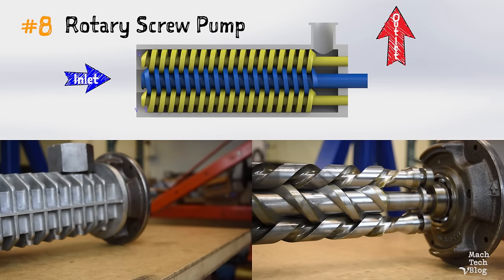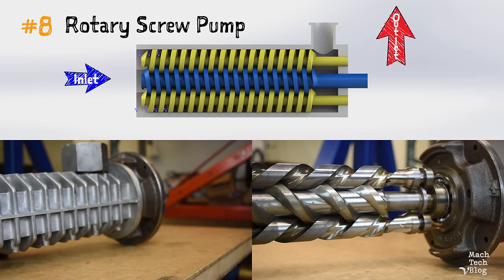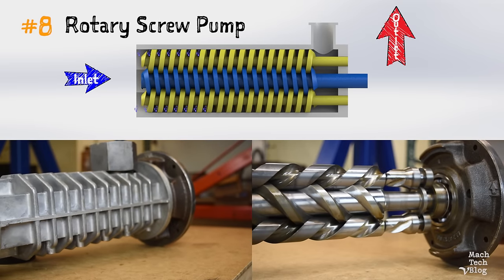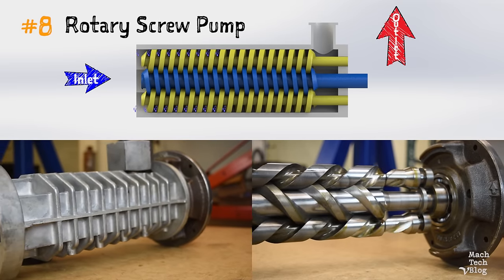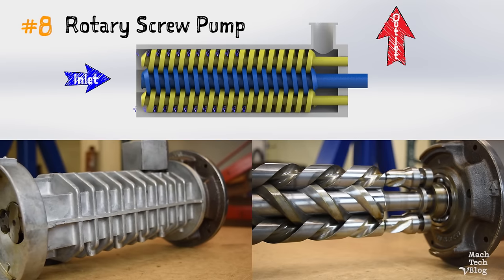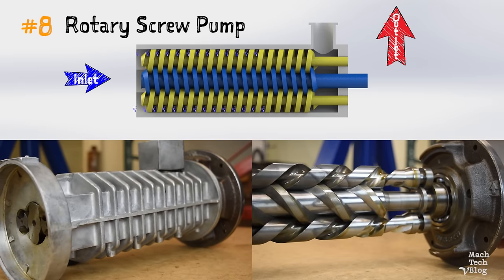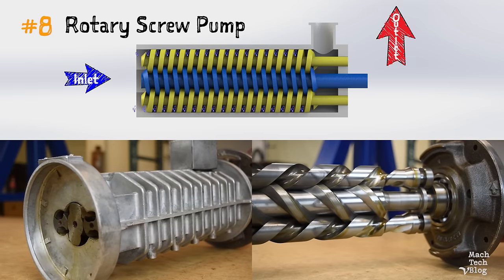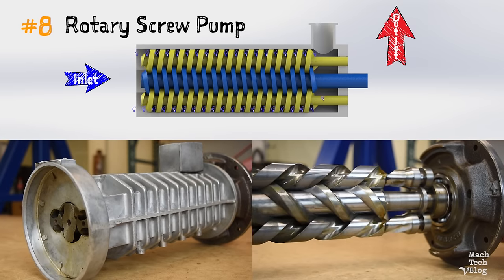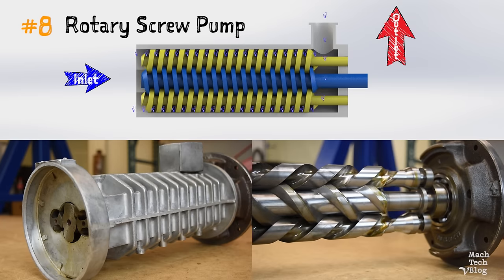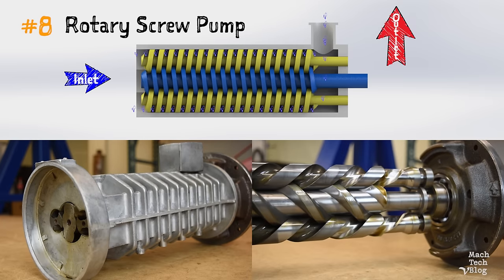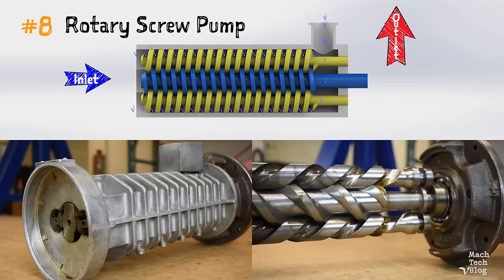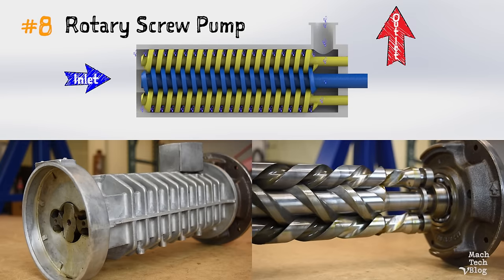Pump number eight is the screw pump. Screw pumps can have a single shaft with large threads on it, but they usually have two or three. The center shaft drives the other shafts like a screw or a worm gear. As the shafts rotate in the housing, fluid trapped in the gaps between the screw threads progresses along the length of the housing and is delivered to the discharge outlet. If you've ever seen an auger or a screw conveyor, this is pretty much the same thing.